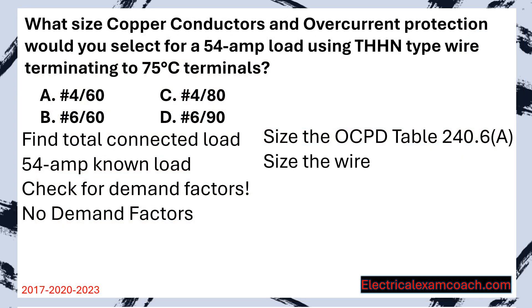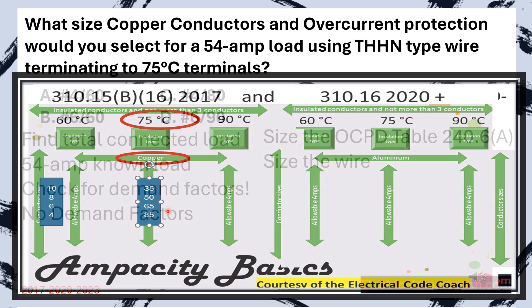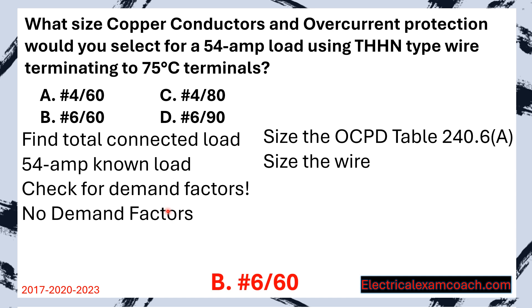Now let's size the wire. For that we head to our primary ampacity table. We start on the left-hand side on the copper side because our question asks for copper, and we're in the 75 degrees C column. We slide down and find a wire that covers the known load of 54 amps, and we select a 6 gauge wire on a 60 amp overcurrent device.